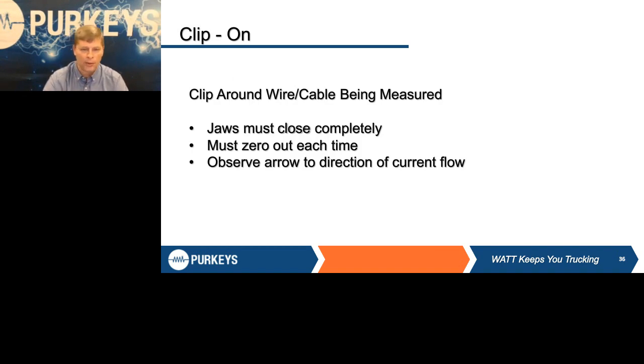If you don't zero it out each time, or if the meter is out of calibration, or a lot of the clip-on amp meters, especially the older ones, had what's called a thumb wheel. You put your thumb on it, you push in, you turn it left, and you calibrate it. What a cantankerous function on a meter, that you turn it one way and it jumps up to positive 10. You turn it back a little bit, it jumps all the way to negative 15. The modern ones now have a 0 button, so you can simply hit the button.